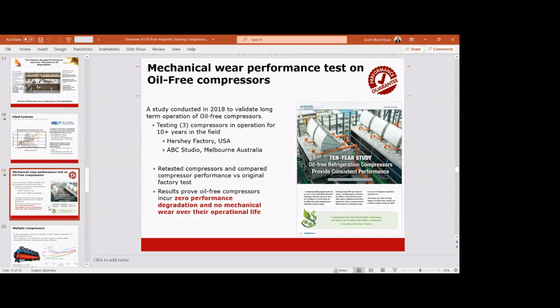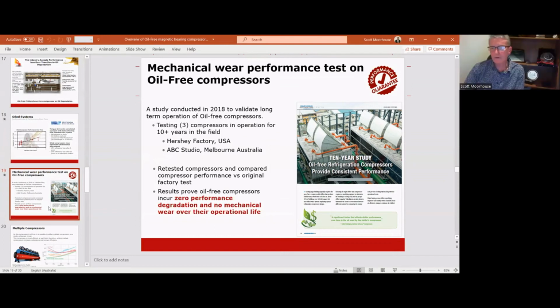The 8.7% wear that we talk about can be due to mechanical losses. There was a study done in the US, a Hershey factory in the US, and a television studio in Melbourne, where some compressors that had been running for over 10 years were taken off the site and taken back to the factory where they were produced. And a performance test was done to see if they'd lost any performance at all over that 10 years. And the results were that they did not lose performance over the 10 years because the magnetic bearings don't have any mechanical touching, so there is no wear inside the compression area. So the result was zero loss of performance in that case study.